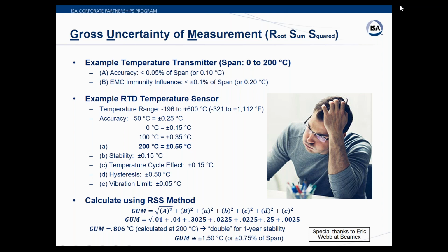So that's a good point. I think this does help us visualize why we can't just take an accuracy statement from a transmitter and then calibrate it to that value. There are so many different things that come into play, and if we calibrate this thing to 0.05% of span or 0.1 degrees Celsius, we're setting ourselves up for failure. So just one other comment is, well, this actually goes back to, is your standard accurate enough? So we'll find that out as well on the next phase here. So thank you, Ned. All right. So one more slide, and then we're going to let Roy take over here.